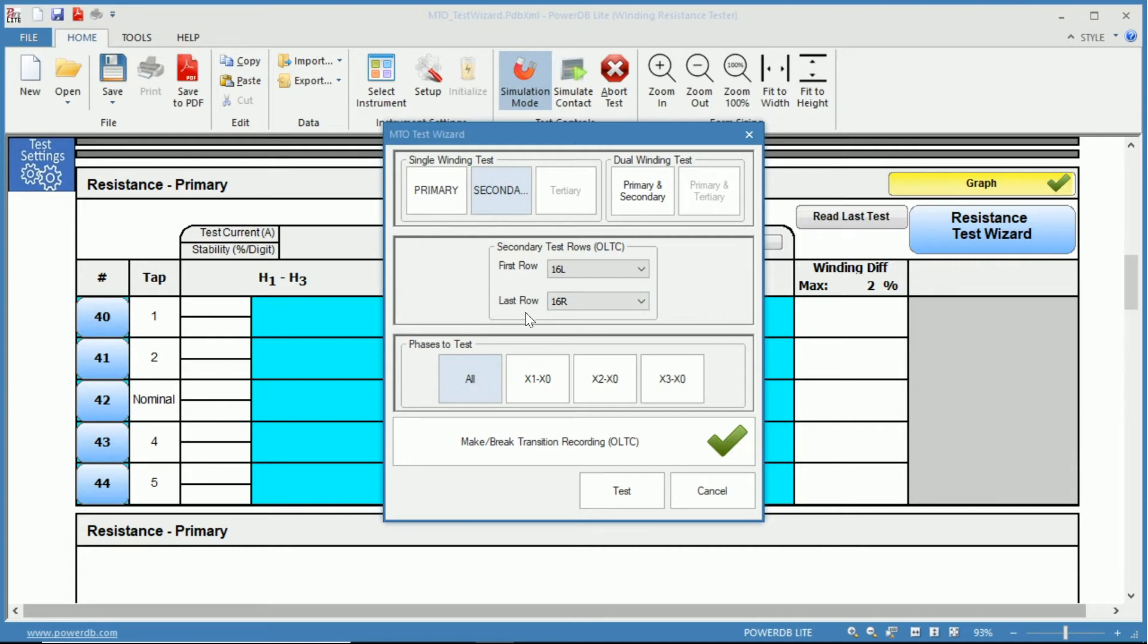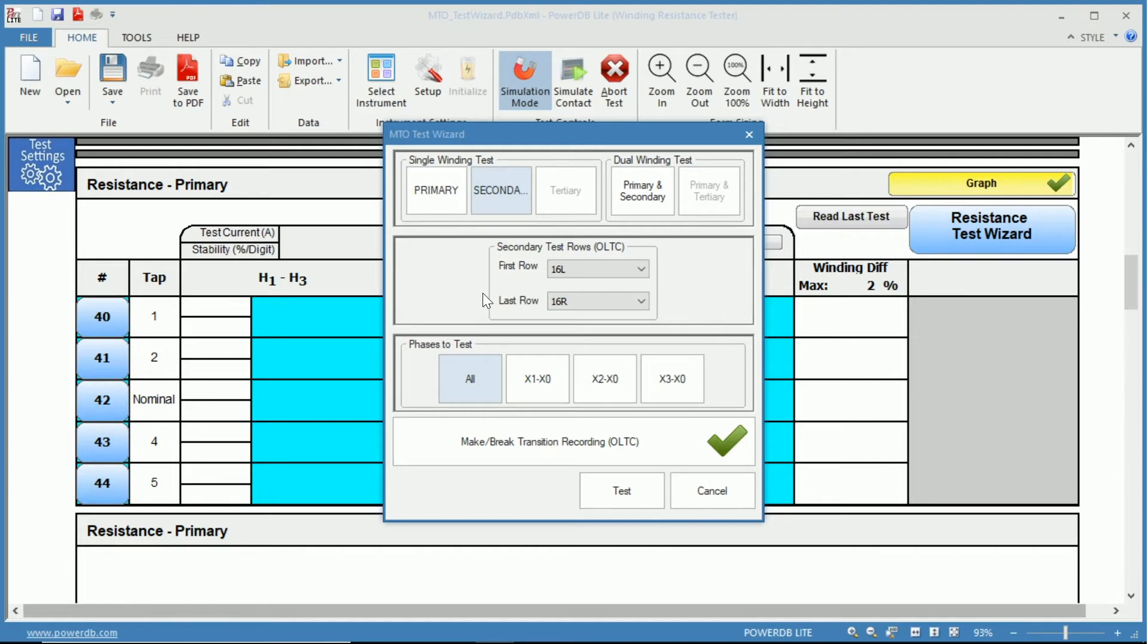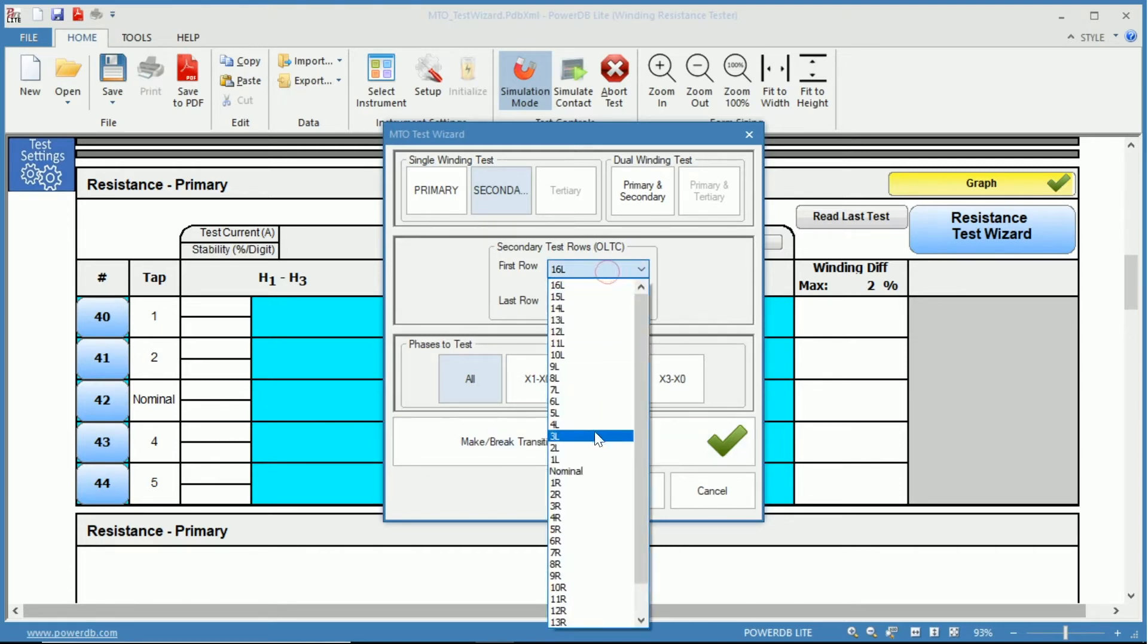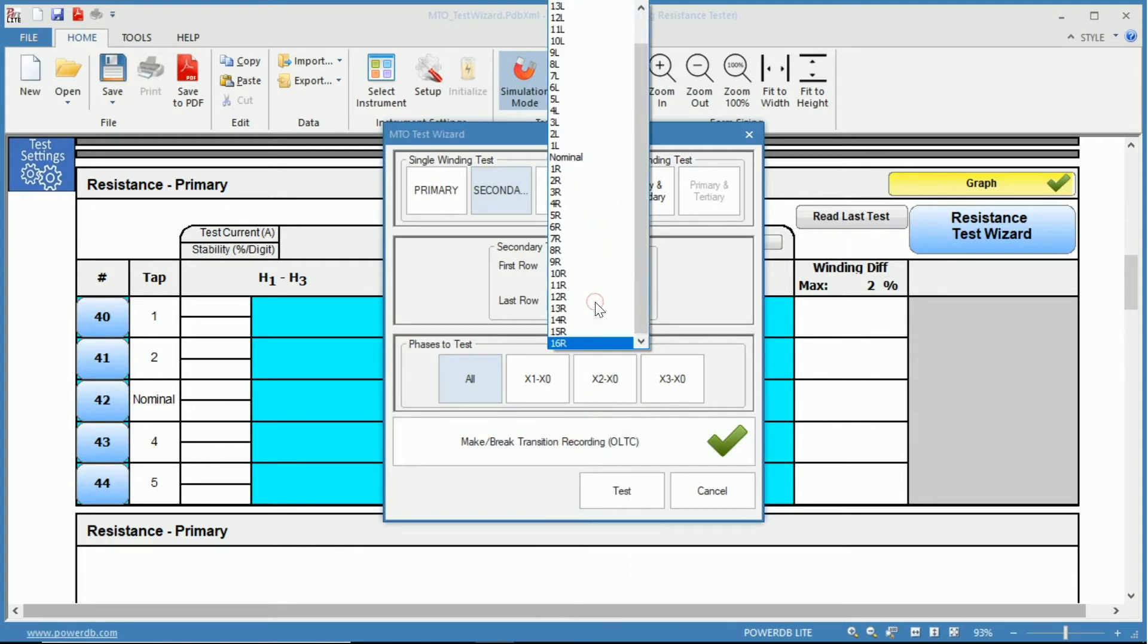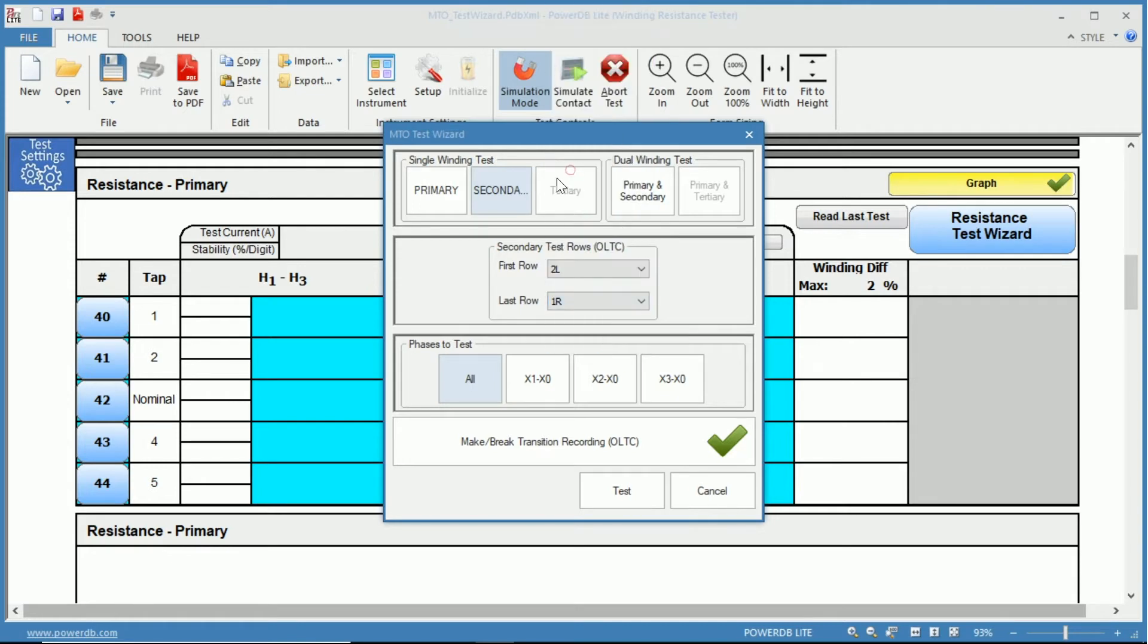Once completed, if you have testing in all phases, it will then continue going 16 raise to 16 lower to keep the direction of flux the same and to reduce the total test time. But you can also select a different range of taps. For instance, for this video, we will select three lower to one raise.